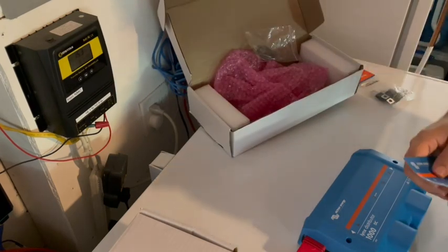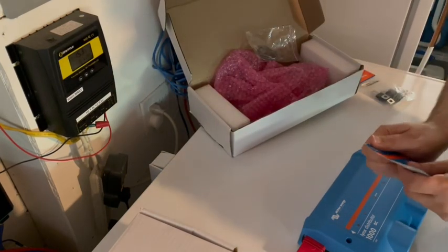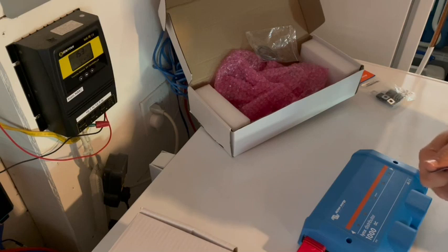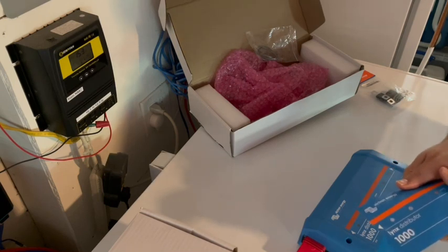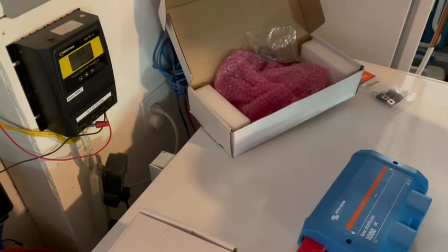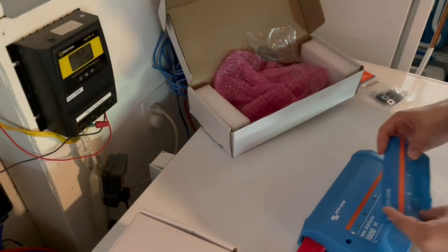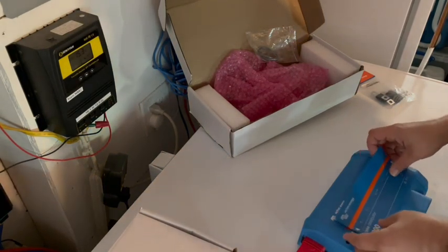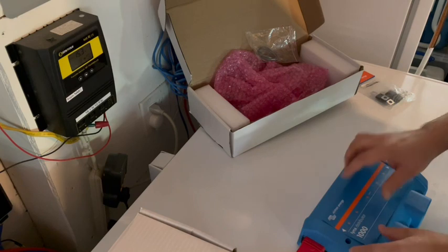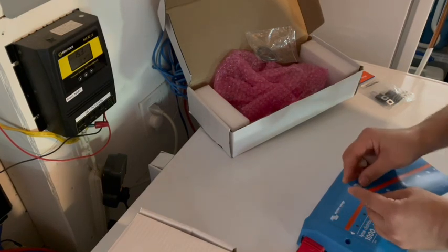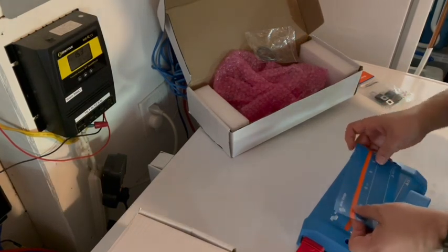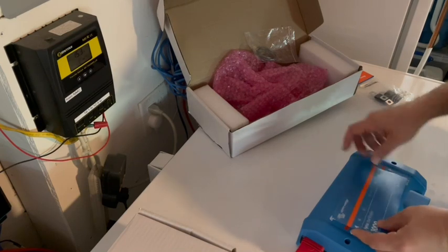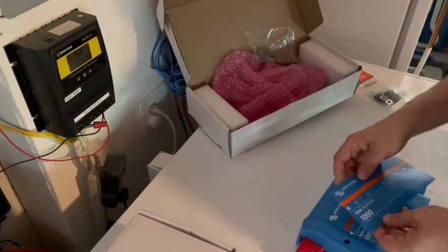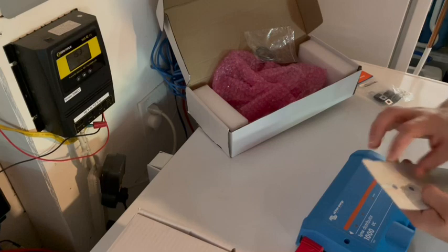That whirring sound was basically the sound of one of my refrigerators starting to draw extra power, so the inverter started whirring. I've seen current bursts as high as 130 amps from a refrigerator starting up, so that exceeds 1 kilowatt, but these 1 kilowatt Renogy inverters can go to 2 kilowatts briefly.